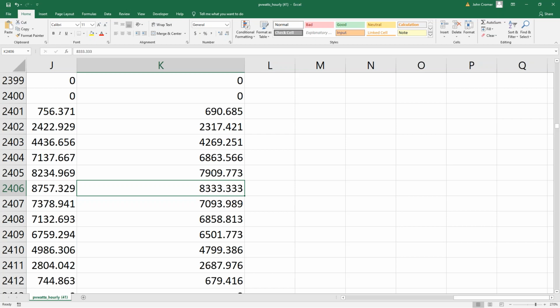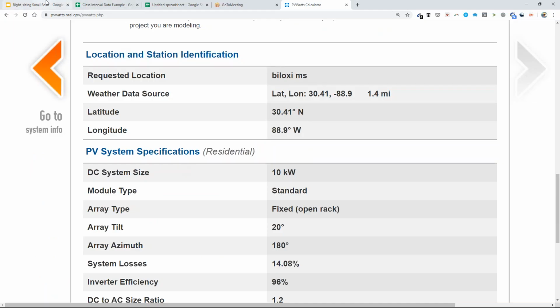If I'm trying to capture every kilowatt hour that comes out of the system, as with a net metered or grid tied system, I could put it on an 8.5 kilowatt inverter even though it's a 10 kilowatt system, and still capture every kilowatt hour at a 15% undersize. In the industry, it's very common to undersize the inverter by 15%, no problem. You can see examples of even greater undersizing, although this technique has diminished in importance as inverters have come down in price.